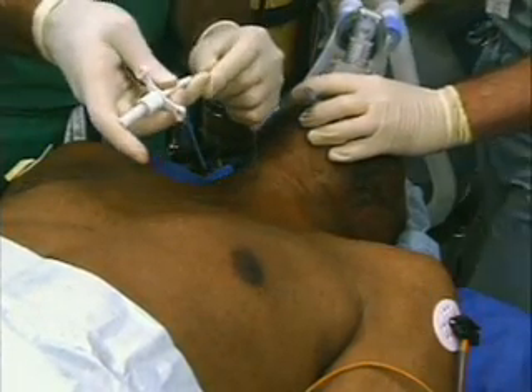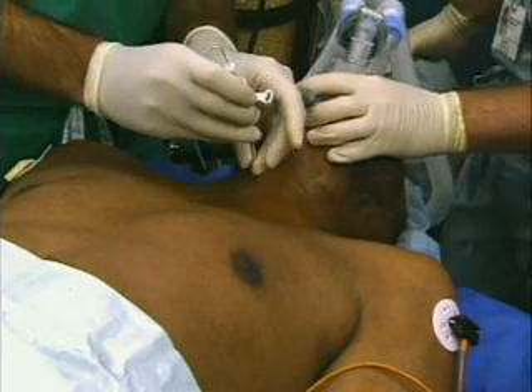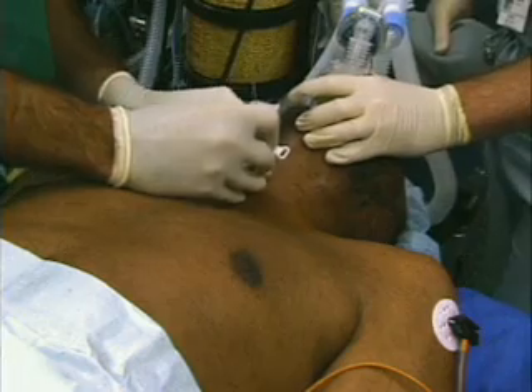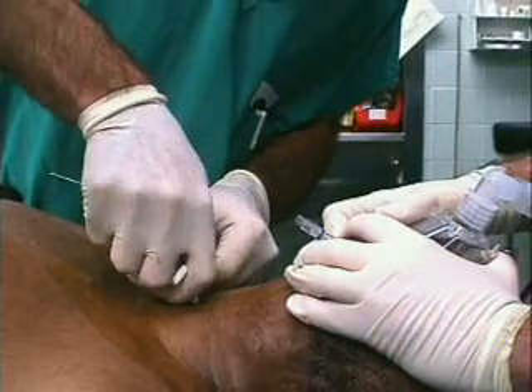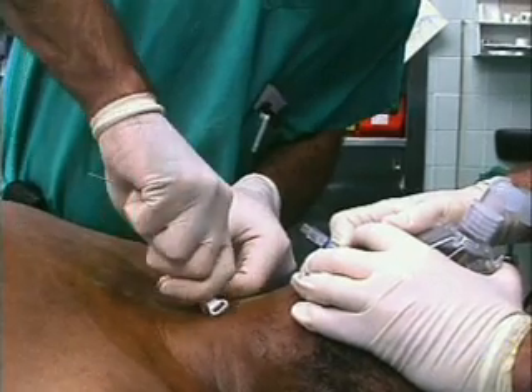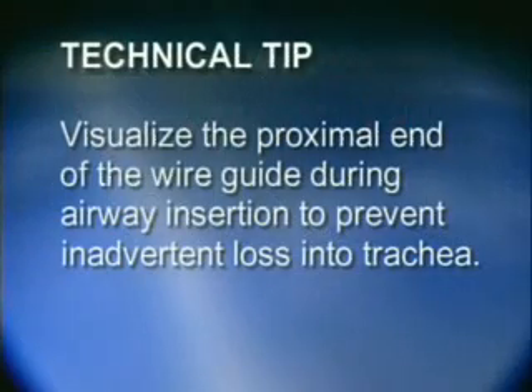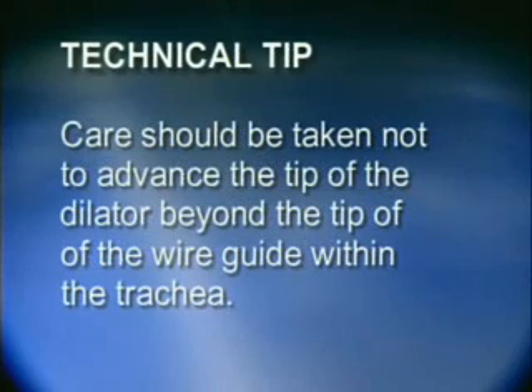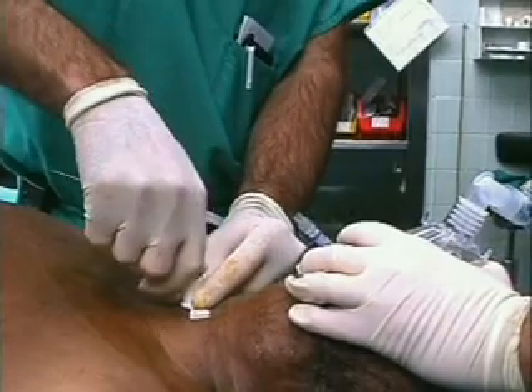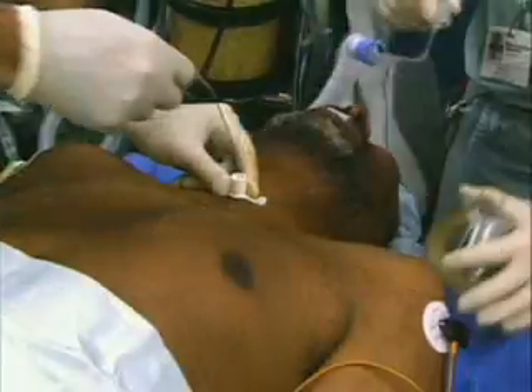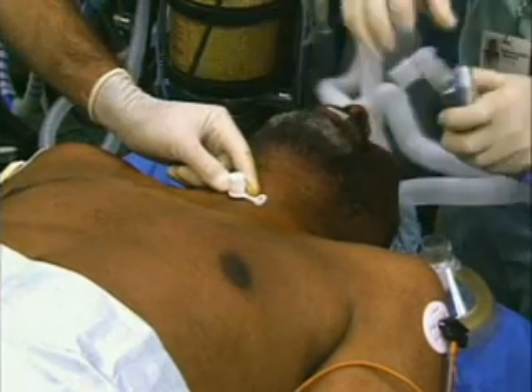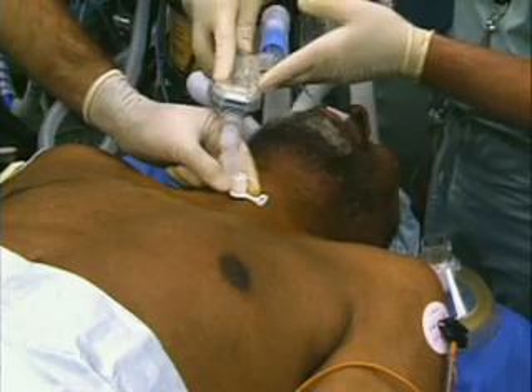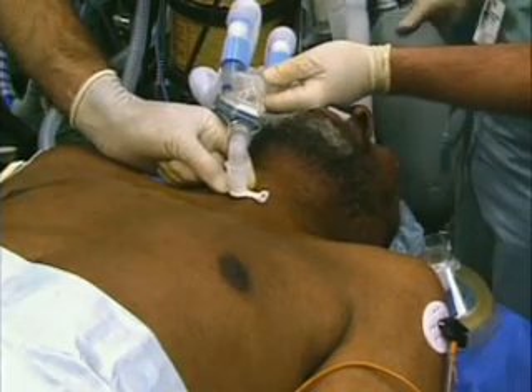The dilator airway catheter assembly is advanced over the wire until the stiff end of the wire emerges from the dilator handle. The dilator airway catheter assembly is advanced over the wire and into the trachea. It is important to always visualize the proximal end of the wire guide during the airway insertion procedure to prevent its inadvertent loss into the trachea. Care should be taken not to advance the tip of the dilator beyond the tip of the wire guide within the trachea. Once the dilator airway catheter assembly is within the trachea, the dilator and wire are removed simultaneously. The emergency airway catheter can then be connected using its standard adapter to an appropriate ventilatory device.